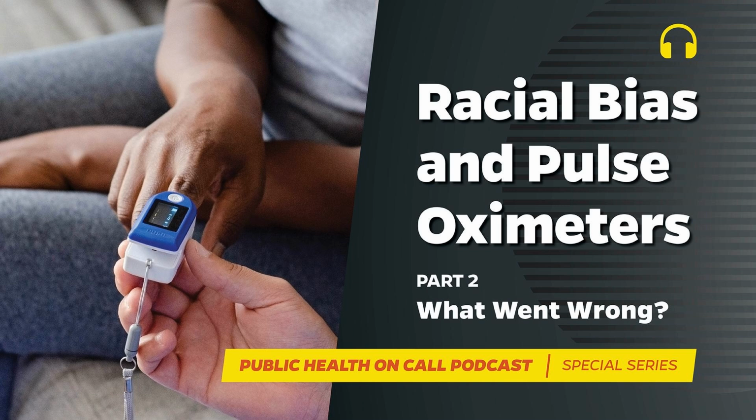Even more recently, in February of this year, FDA advisors from the Anesthesiology and Respiratory Therapy Devices panel of the Medical Devices Advisory Committee proposed new recommendations for pulse ox clinical testing. They recommended increasing the number of patients included in studies from at least 10 to 24.